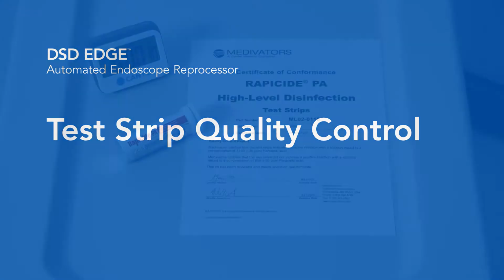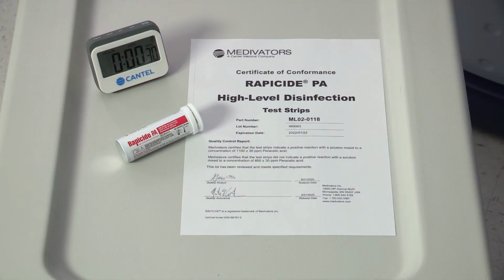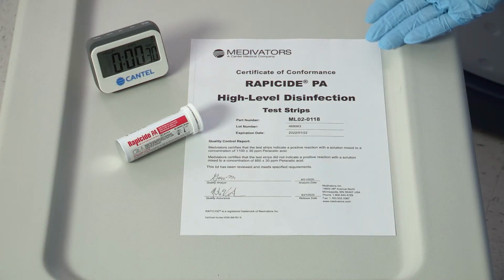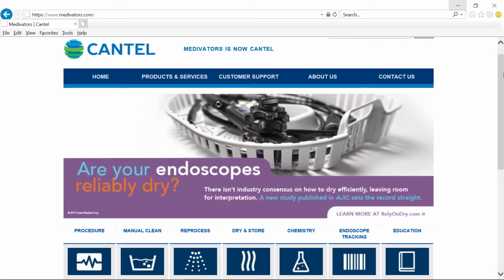A quality control for the test strips must be performed prior to use. Cantel provides an online library of lot numbers tested prior to being shipped to customers. You may see this referred to as Certificate of Analysis or Certificate of Conformance. When a new bottle of Rapicide PA test strips has a new lot number, the quality control must be confirmed.